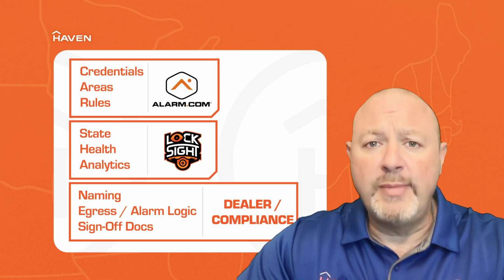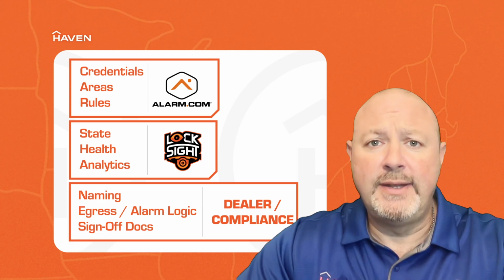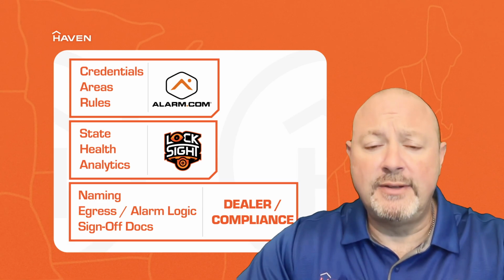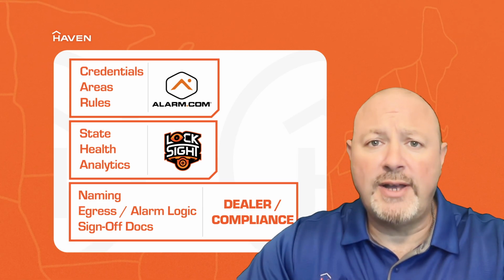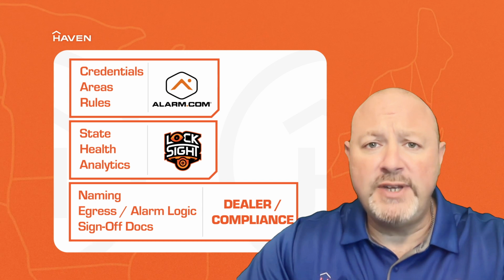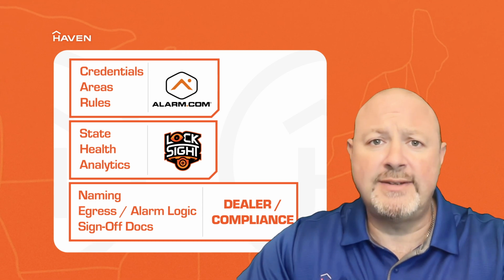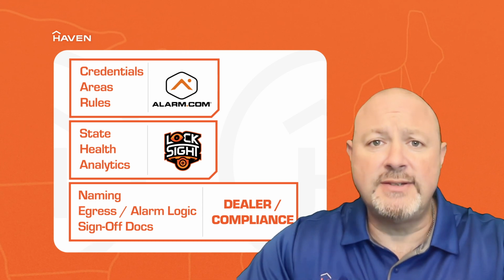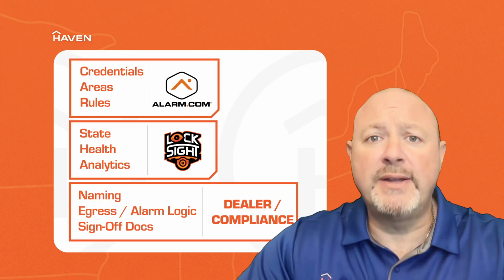Golden rule: maintain free egress. Define behavior for 3 states: normal operation, power loss, and fire alarm, and prove each one on site with a witness test. The authority having jurisdiction, spelled AHJ, will expect this.